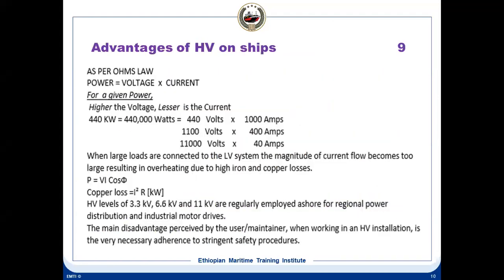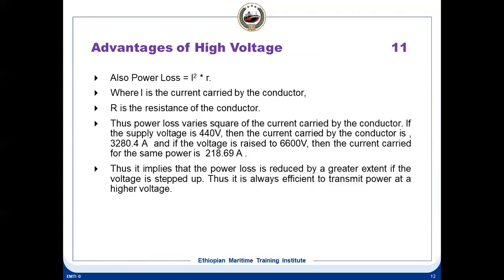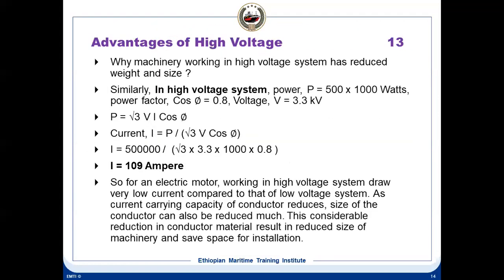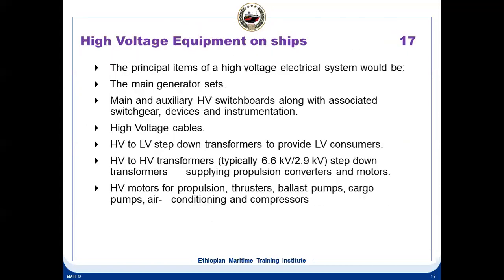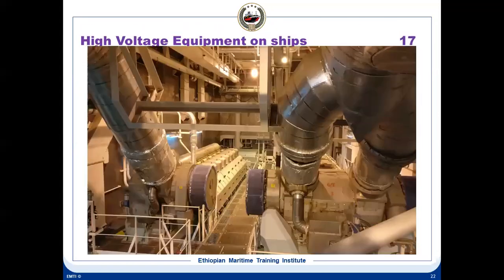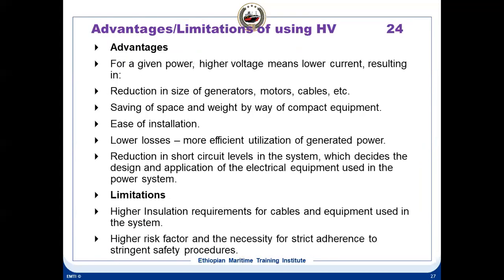Advantages of high voltage on ship. What are the advantages of high voltage on ships? Advantages and limitations, very important. For a given power, the higher the voltage, the lower the current. So it will result in reduction in size of generators, motors, cables, ease of installation, lower losses, reduction in short circuit levels. Very important points. Limitations: higher insulation requirements, higher risk factors and strict safety procedures.